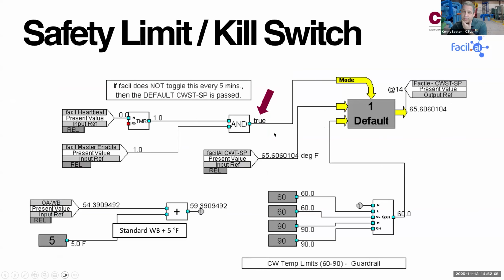How are we doing it so that we feel safe, right? Because that's a big thing. People are worried that the AI is going to take over, that it's going to break your equipment, going to break something. So we wrote a real simple program. We call this input the heartbeat. If it doesn't see a signal from the AI every 5 minutes, then this statement goes to a 0 and we end up false. If this is false, we come back to our old settings, 5 degrees above wet bulb.